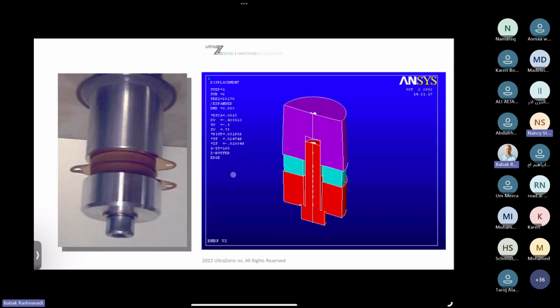Now here on the left side, you see a picture, really a picture of a transducer, and this transducer has metal parts. A stainless steel part above, a stainless steel part on the bottom, and in between you have the piezoelectric part. This piezoelectric part is the most important part of your transducer to create the right frequency of your cavitation bubble. So you will see it also later.